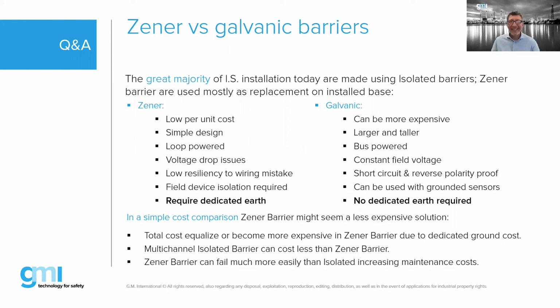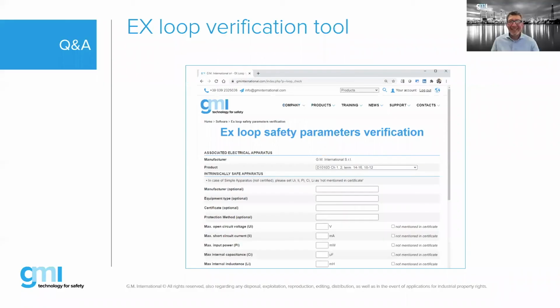Right. We have many questions about cabling. I want to go back here for a second to this question which somebody asked about what if we cannot manage to fit in this table? Well, there's not much you can do. If the parameters do not match, unless it's a cable that introduces an error, meaning that the longer the cable, the more capacitance and inductance you have, you might have to shorten your cable. But if the two devices, the barrier and the field device of any sort, do not match, well, they do not match. You need to look for a different device or a different barrier. Okay, let me go forward.